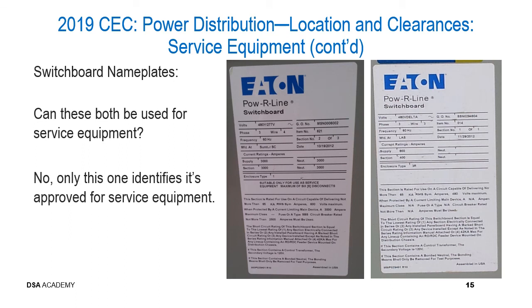We're going to talk just a little bit about service equipment, primarily switchboard nameplates, and we have a simple quiz here. If you were to look at both of these labels, they're almost identical. The question we're going to ask is, can these both be used for service equipment? I know it's a little bit difficult to read the information on these two labels, and I apologize for that. However, if you look very closely, you can see the one on the left has some verbiage right in the middle in the comments section. This is what identifies that this particular panel or switchboard can be used as service equipment, and what it says is, suitable only for use as service equipment.